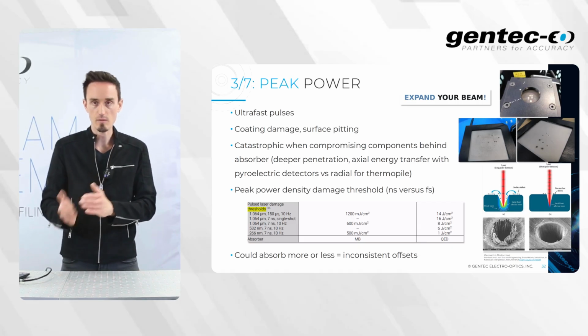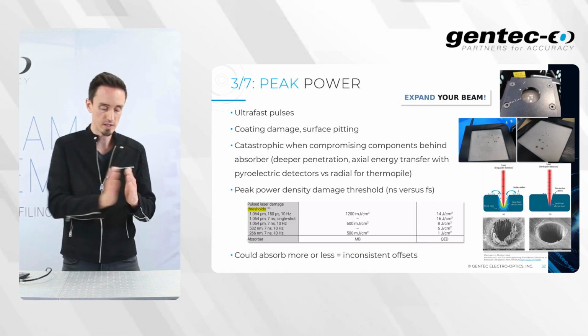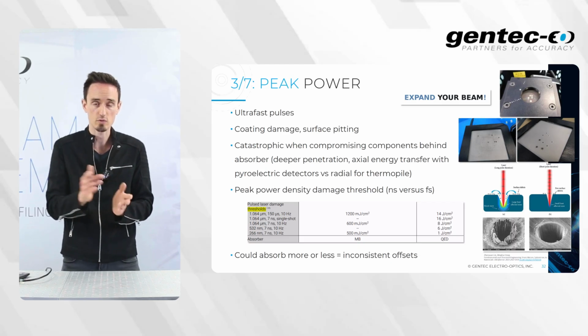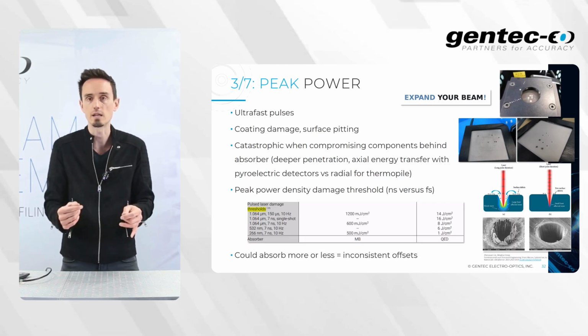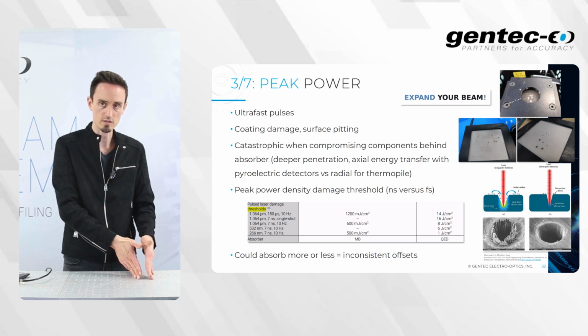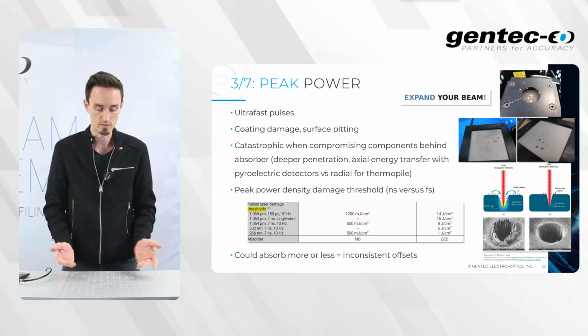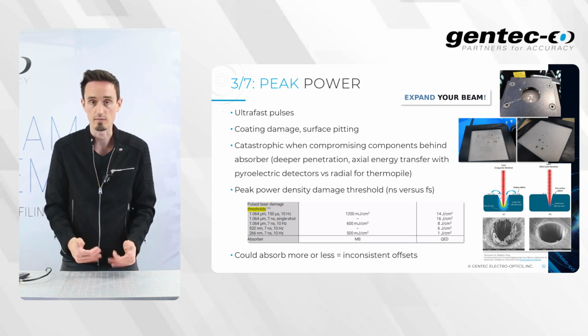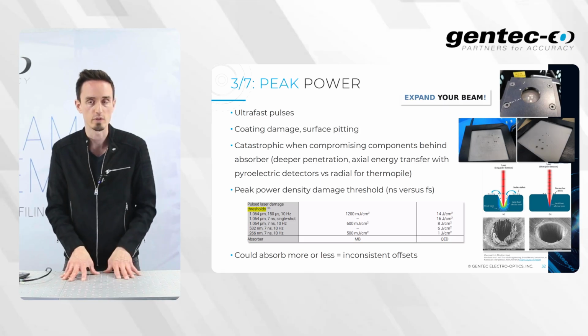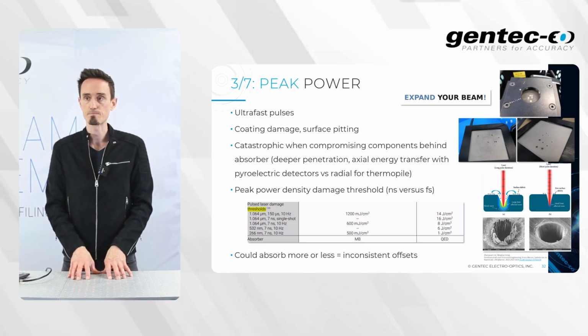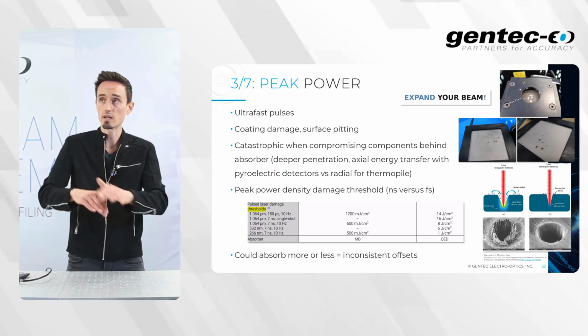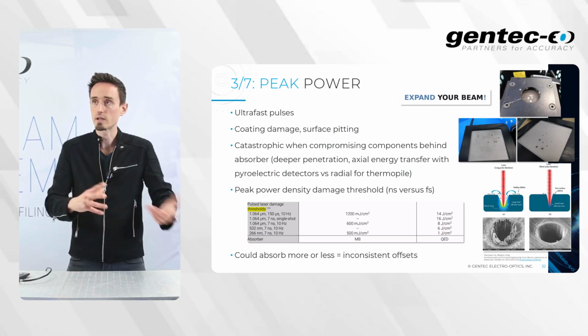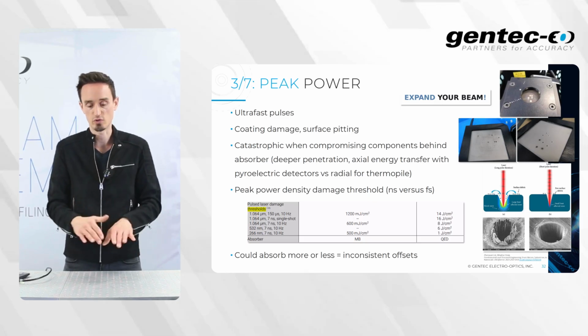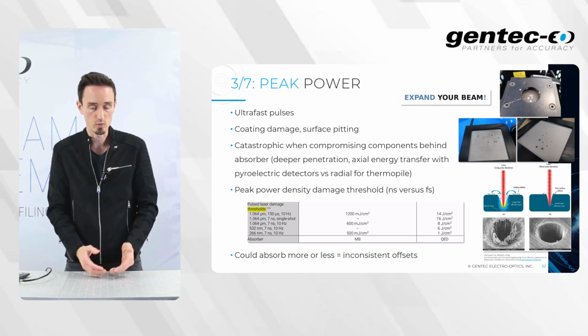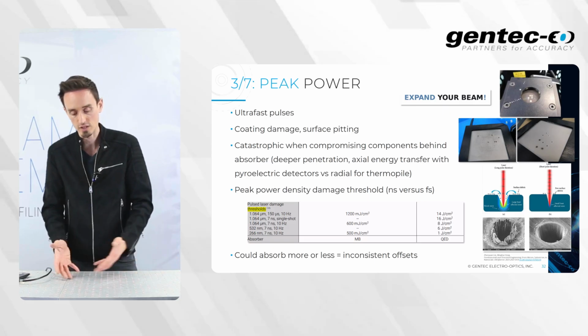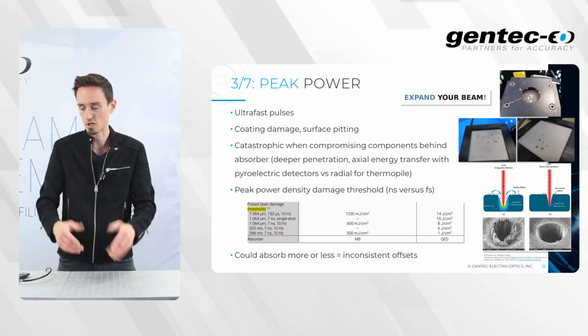If you take this number and you go from nanosecond to picosecond pulses, as a rule of thumb you take the damage threshold number and divide it by 10. If you go from pico to femto, next step, you take the number you got and divide it by 10 again. This is the rule of thumb, but we can confirm that for exact specifications. Then, again, if you have markings, looking either black or white or a shade of gray, on the surface, the absorption locally will be different, so that will result in inconsistent offsets for your measurements.